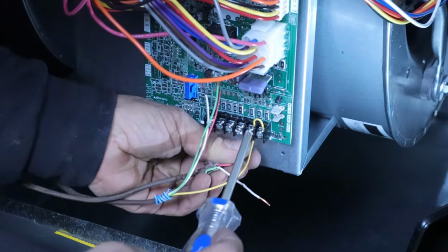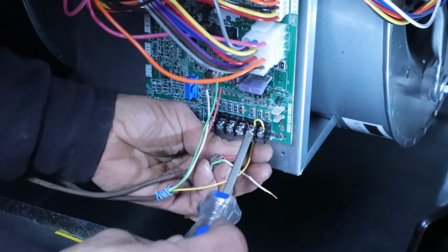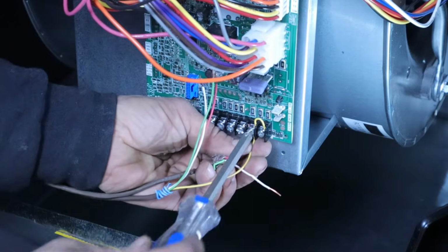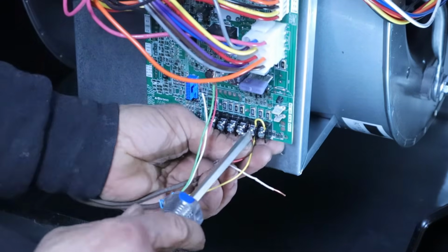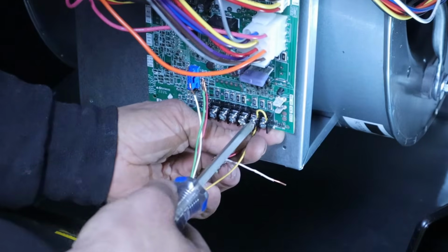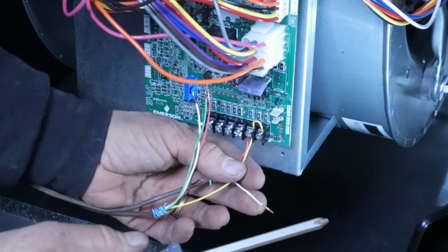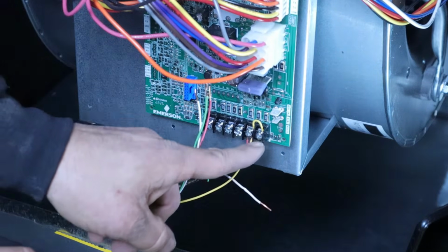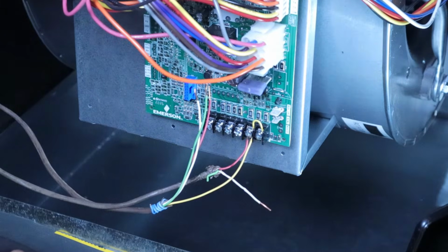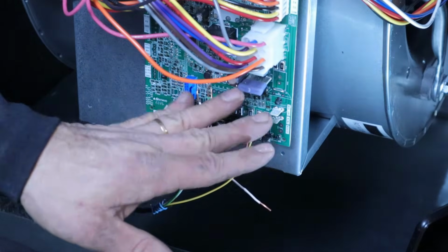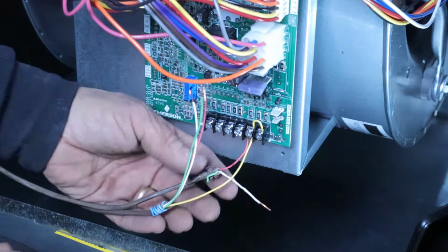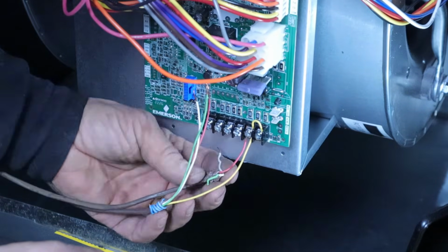As it's powering the Y1 terminal, it's also going to send 24 volts out to the condensing unit outside, and that's going to close the contactor that allows the condensing unit to start up. It's also going to jump over to Y2, and that's going to make sure that this blower here is always running at second stage cooling, because we don't have a staged thermostat here.